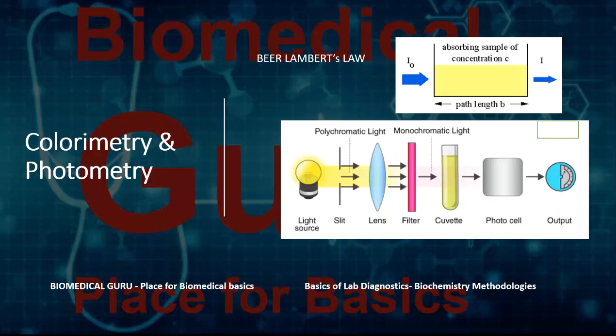Next we'll see the basic mechanism or the skeleton diagram of a colorimeter or a photometer or a semi automatic biochemistry analyzer. Here we see there is a light source. The light source will emit light, and there will be a lens mechanism which will convert the diverging light into a pencil beam, because when light emerges from a bulb, it will go in different directions, and here we are supposed to have a light which will pass in one direction. For that we need a lens mechanism.